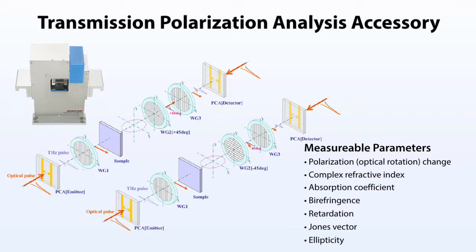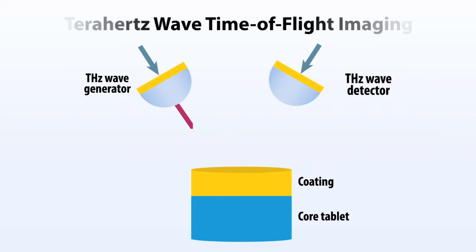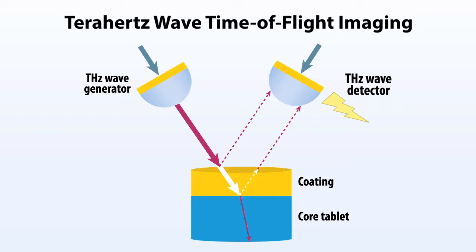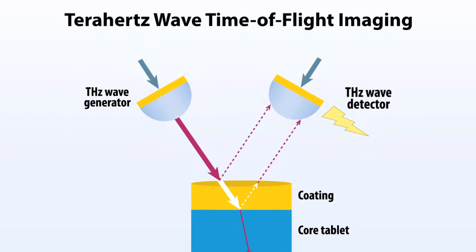Polarization studies can provide information on the chiral purity of enantiomers and the optical anisotropies of crystalline materials. Terahertz radiation is partially reflected at interfaces where there is a change of refractive index, but passes in straight lines through pharmaceutical materials. This combination is what makes it possible to measure coating thickness without the calibration required by other spectroscopic techniques.